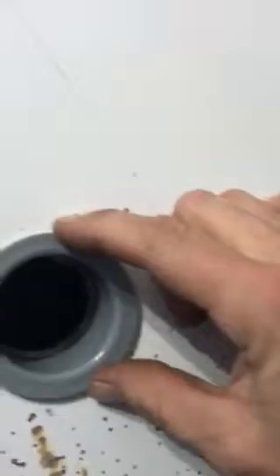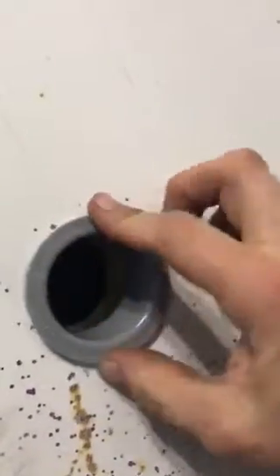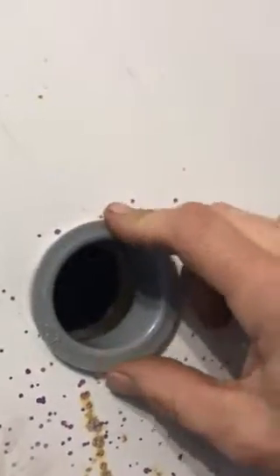After that, I'm going to add this plastic reducer for conduit — plastic conduit. I'm going to put one inside, one outside, and fill this with spray foam, because you want to have this airtight. Otherwise you could get condensation in your insulation and have issues. So I'm going to get all this siliconed up, spray foamed, airtight — and then we'll look at how I'm going to do my controls for it.